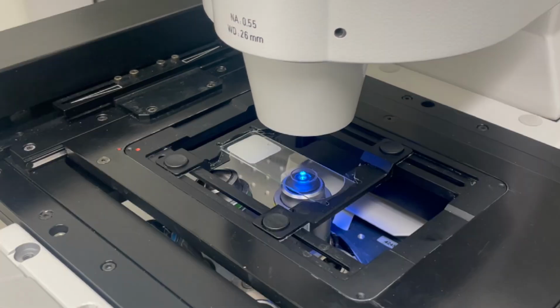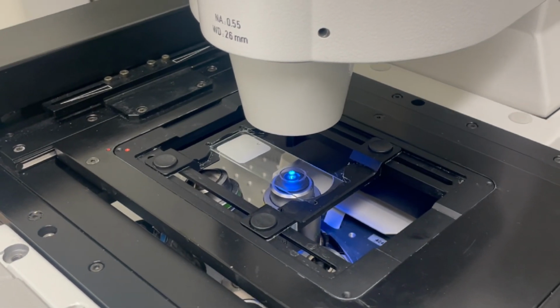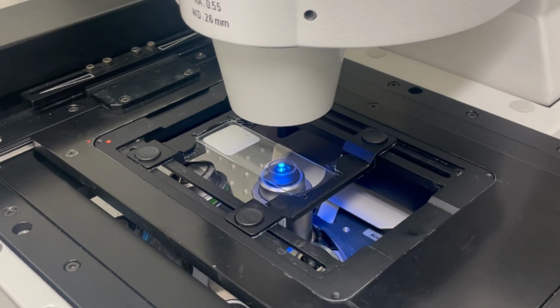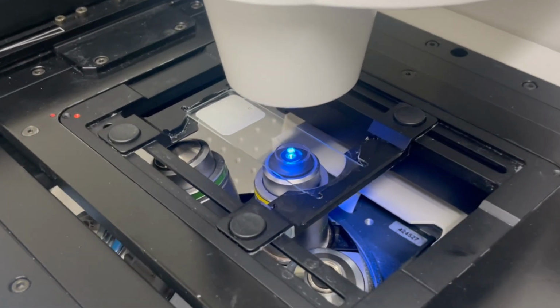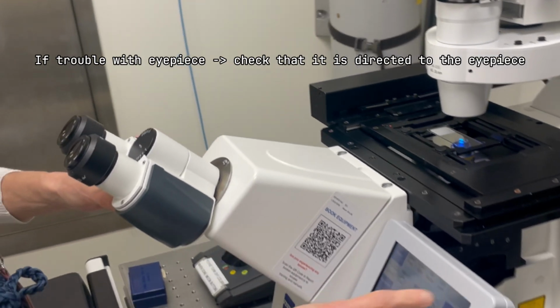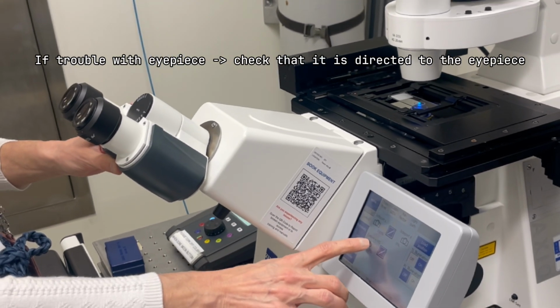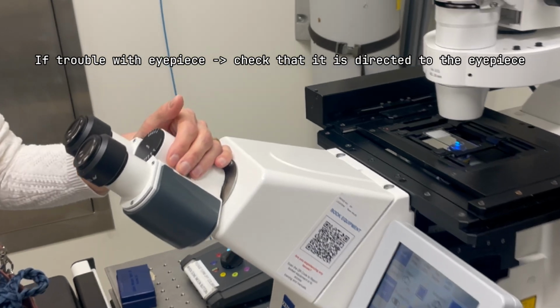If you don't see any light at the sample plane, that's an indication that the light is not on, whether it's the LED or the laser. If you're having trouble viewing it at the eyepiece, you want to make sure that the light is directed to the eyepiece.